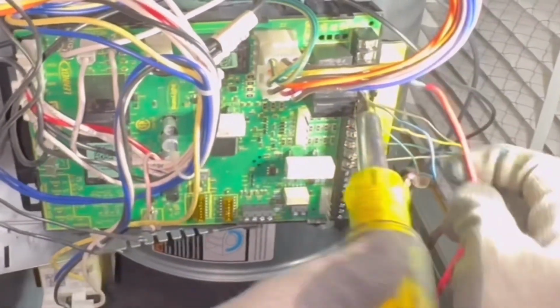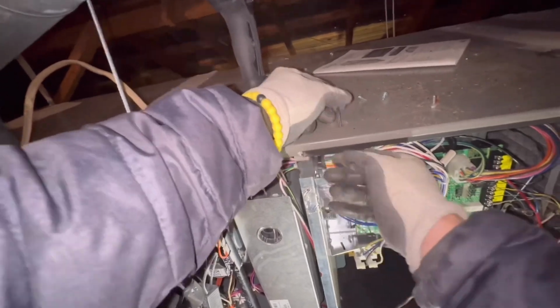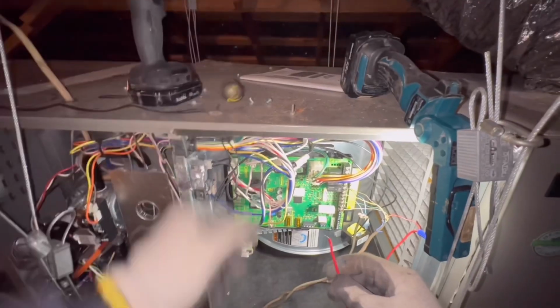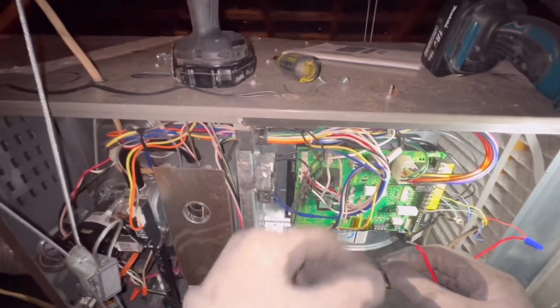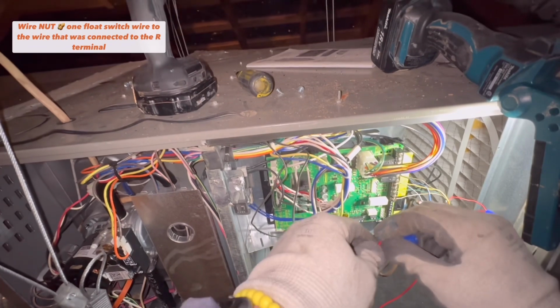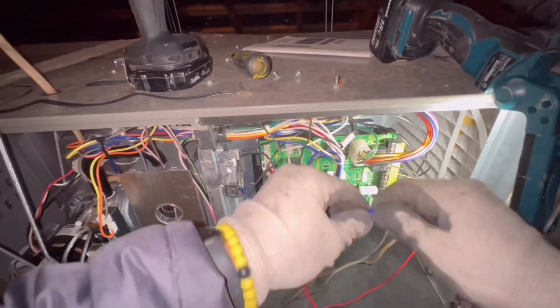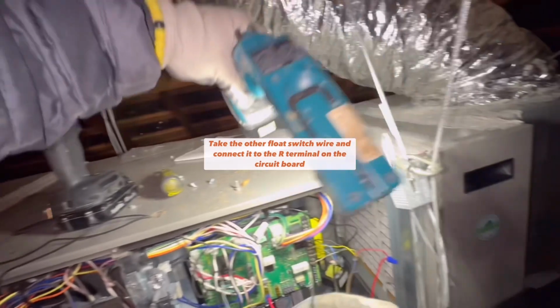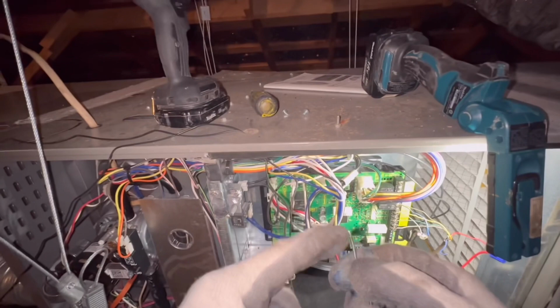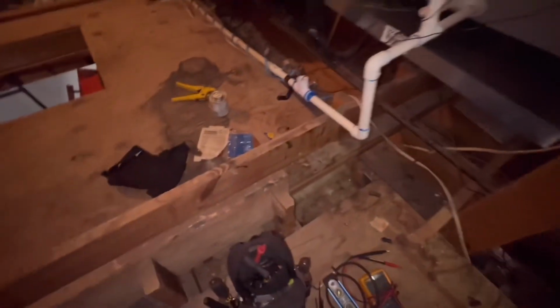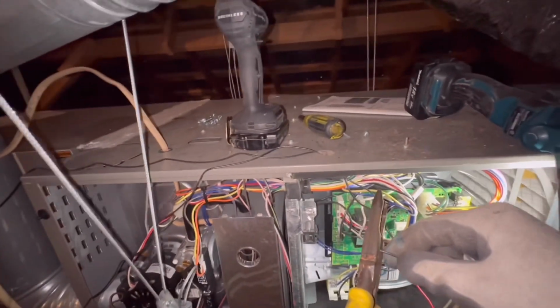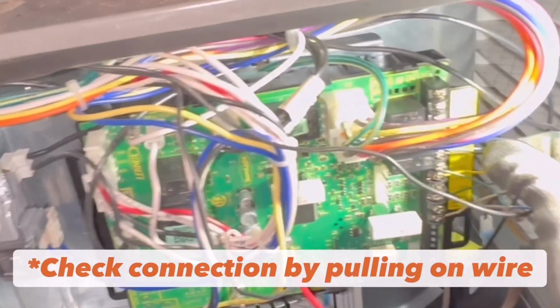After you have disconnected the R wire at the circuit board, make sure you push your float switch wires through the furnace cabinet. You don't want to have to rewire it. Let me repeat this step. You're going to wire nut one side of your float switch to the wire that was connected to the R terminal. Next, you're going to take the other wire from your float switch and you're going to connect it to the R terminal on the circuit board. I always like to pull on the connections a little bit to make sure they're tight.